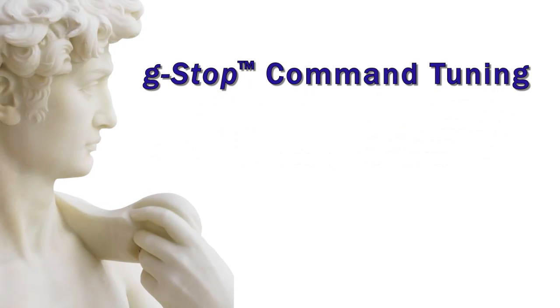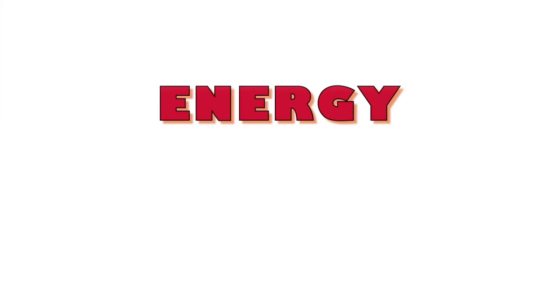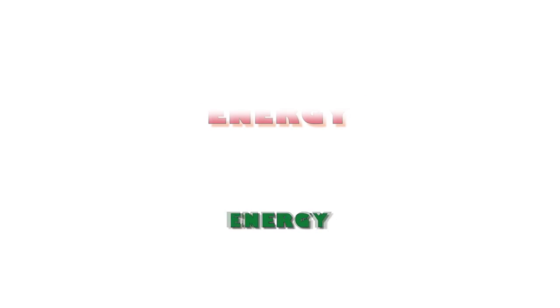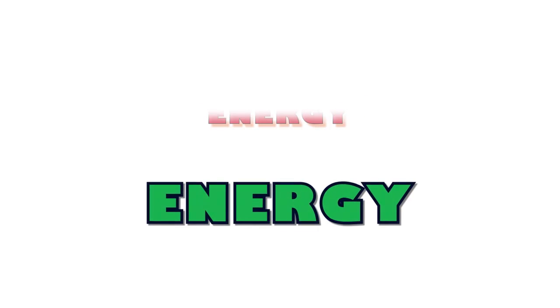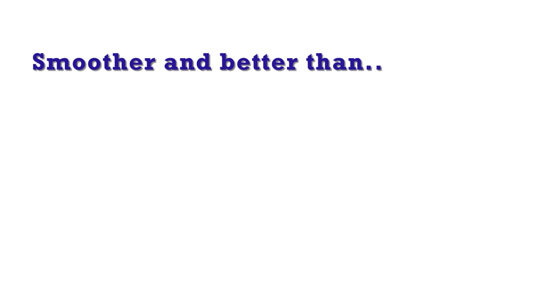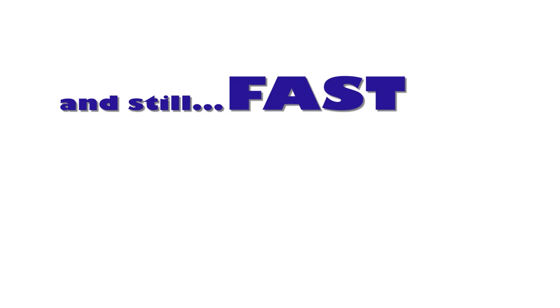G-Stop Command Tuning sculpts traditional commanded motion profiles in such a way as to remove energy from the profiles where there are machine resonances, and concentrate energy where there are none. This is smoother and controls machine vibration much better than S-curves or jerk limited profiles, while still allowing fast moves.